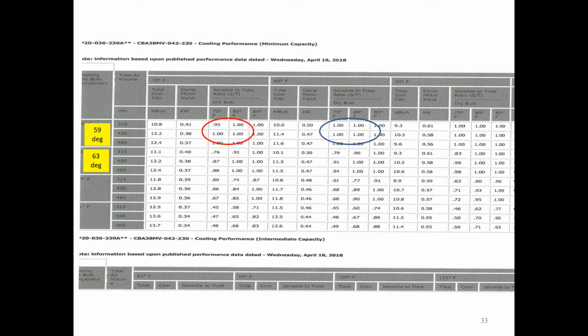At a 59 degree, off to the left, or a 63 degree wet bulb, which is going to be right around when the house is around 50 to 55% humidity, that's about where it's going to fall with a wet bulb temperature. If you go across on a 75 degree day at low end, let's say, I think this is a 3 ton. It is a 3 ton with a 3.5 ton air handler match. So on that low end, we're doing 1 ton, right? So we'd be right around 400 CFM. And if you come across here at 450 CFM, we're doing 100% of sensible. Okay, 100% sensible, zero humidity removal at that point on low stage.